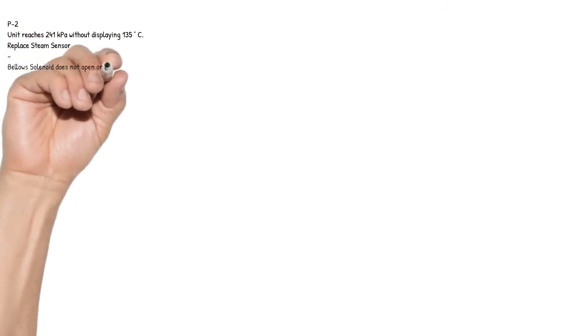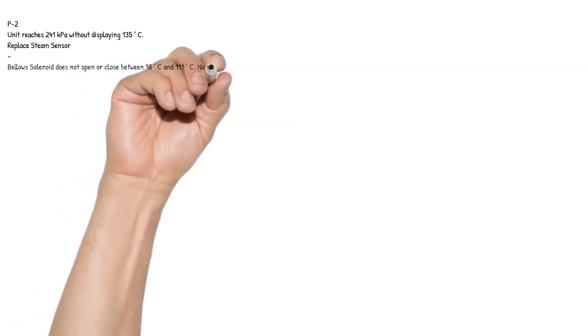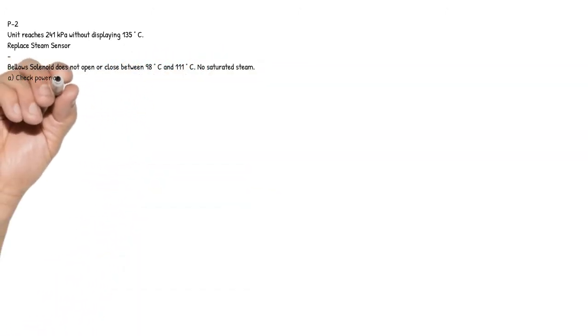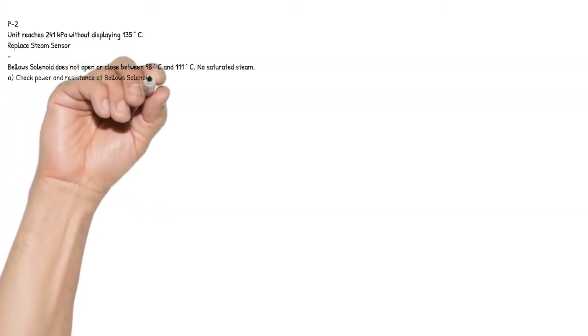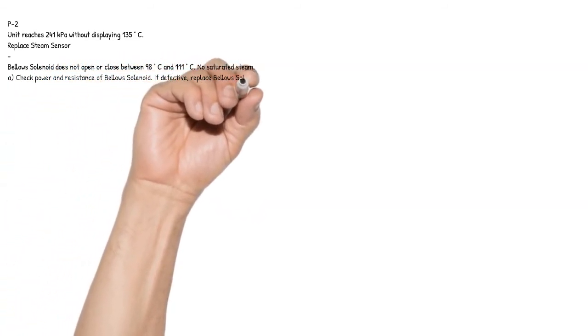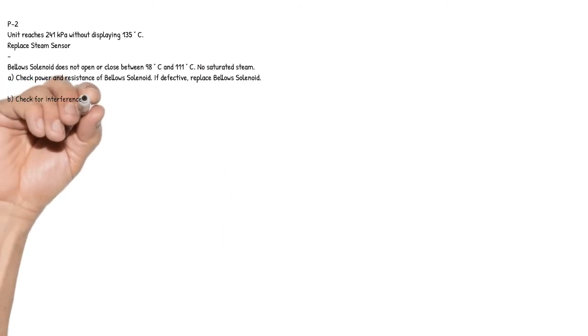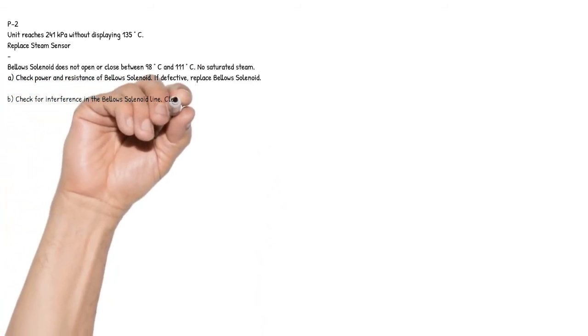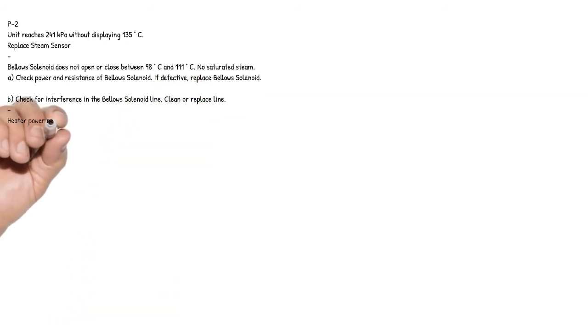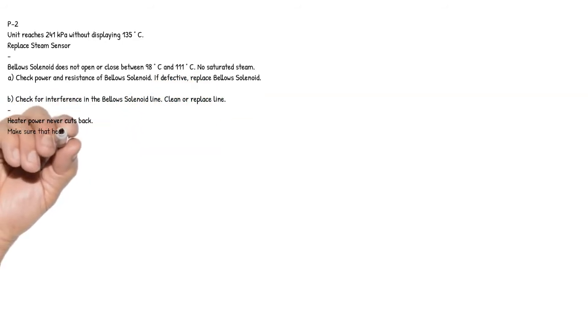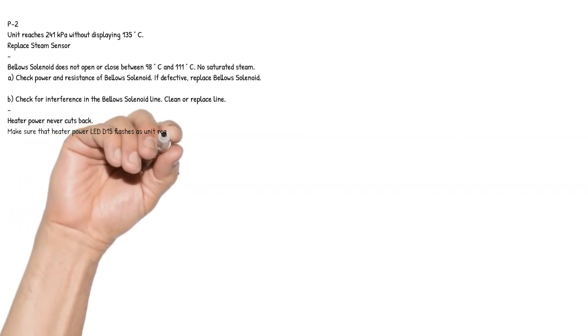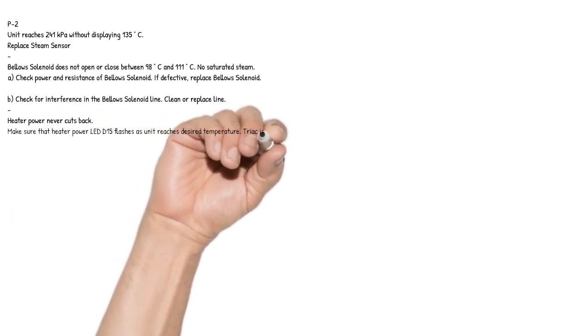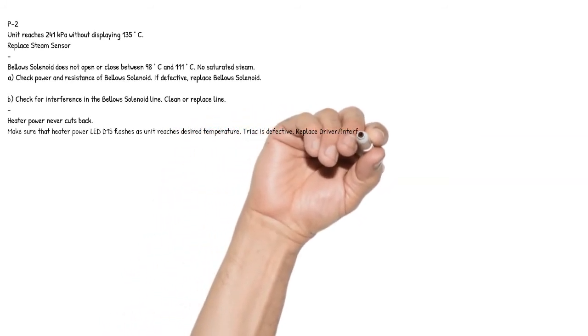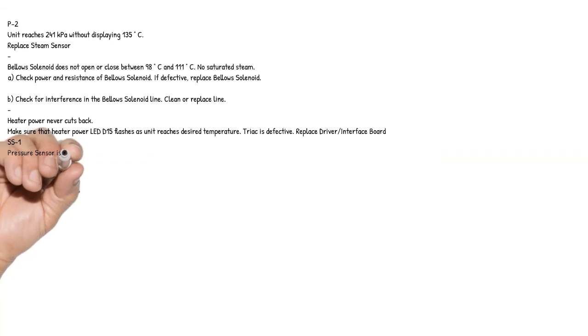P2. Unit reaches 241 kilopascals without displaying 135 degrees Celsius. Replace steam sensor. Bellows solenoid does not open or close between 98 degrees Celsius and 111 degrees Celsius. No saturated steam. A. Check power and resistance of bellows solenoid. If defective, replace bellows solenoid. B. Check for interference in the bellows solenoid line. Clean or replace line. Heater power never cuts back. Make sure that heater power LED D15 flashes as unit reaches desired temperature. Triac is defective. Replace driver/interface board.